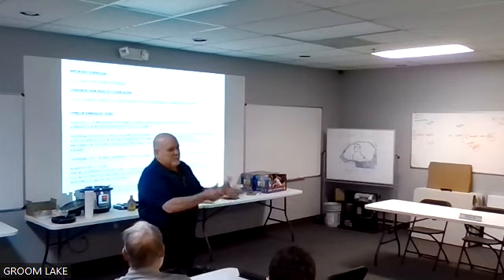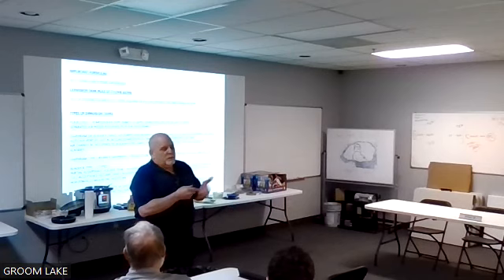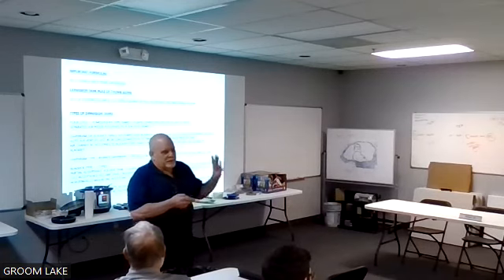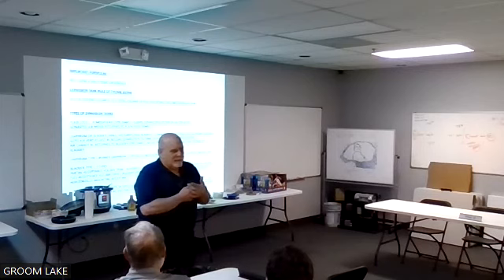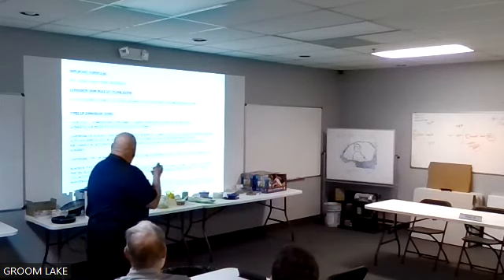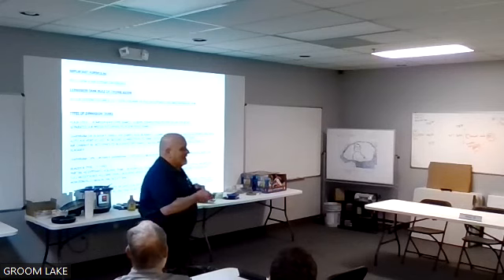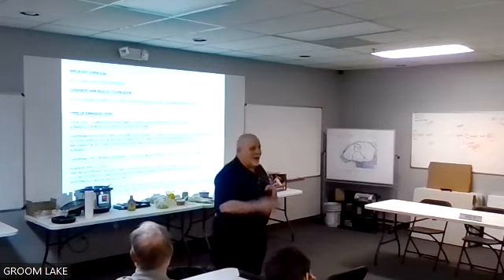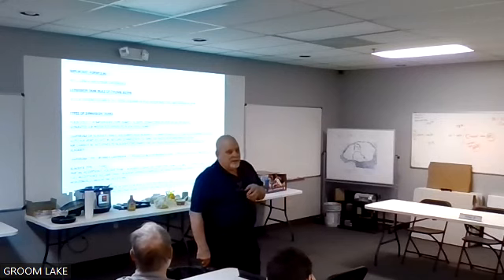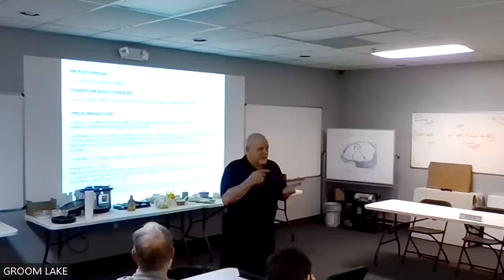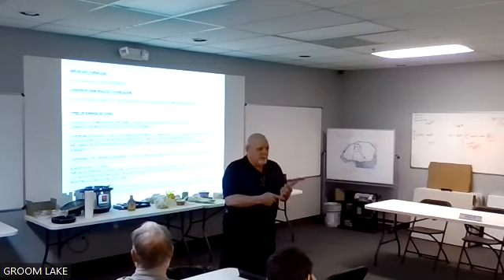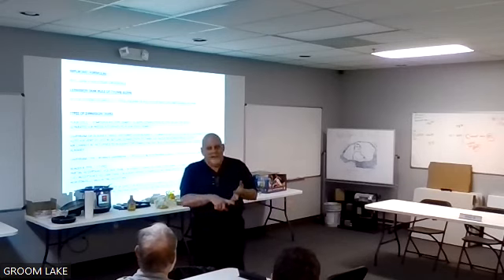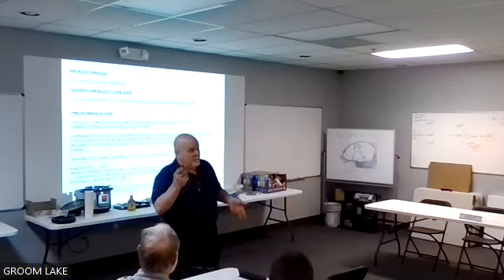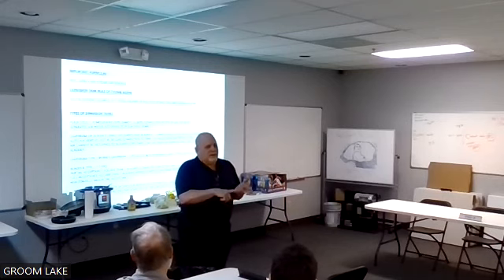But my expanded volume can't be bigger than that bladder. And we'll get into that more as we go along here. You'll see, I've got pictures, and down at the bottom, it's talking about ASME code. In the state of Ohio, anything over 199,000 BTUs on a heating system requires an ASME coded tank. And it's all based on your system height and what your operating pressures are. Standard is 125 PSI ASME. So we also offer 150 pound ASME, 250 and on up. But for the most part, 125 or 150 covers 95% of what you do.